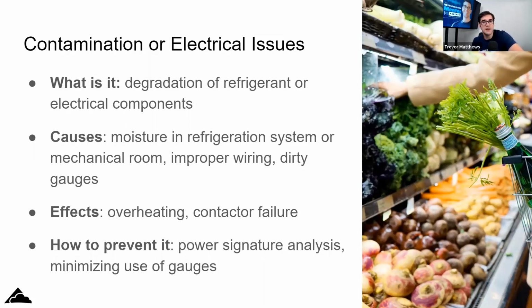And I see a lot of misdiagnosing electrical failures for sure out there because you need to dive into that root cause. And like we're talking about contamination, Joe had a good point about acid starting. So from day one, if the system is not installed properly, if you don't pull a proper evacuation down to 200 microns or 500 microns and holding there, and you have moisture in the system, the compressor doesn't fail after a week, after 2 weeks, after 6 months. Sometimes it's 4 years down the road because of that day one installation, even though it ran for 4 years and kept temperature. Each day, each week, each month, it started to degrade that oil a little bit, and then you get something called copper plating, which eats away at the windings, and you can see it inside the compressor.